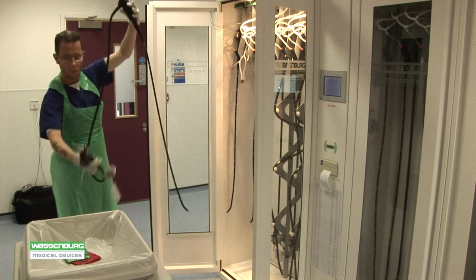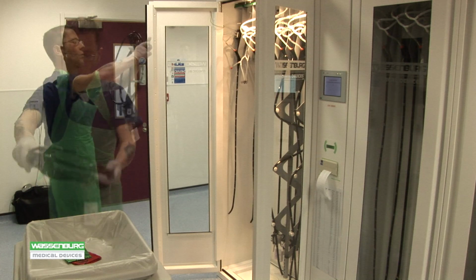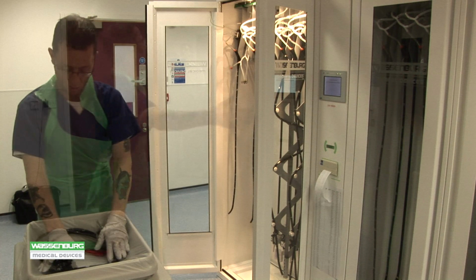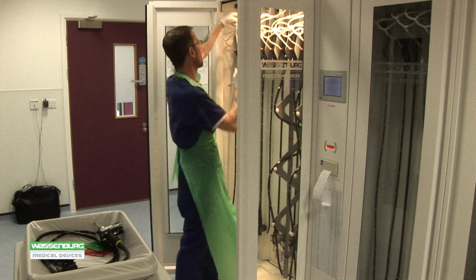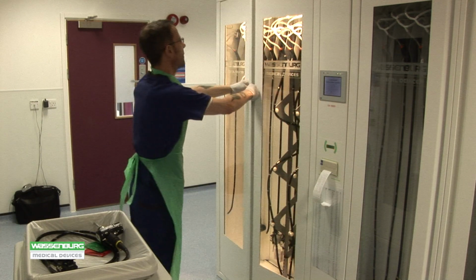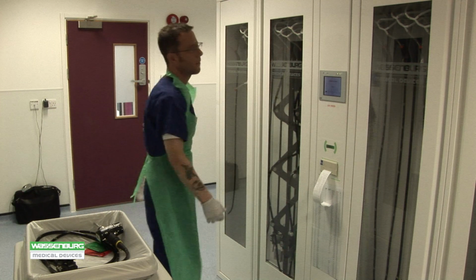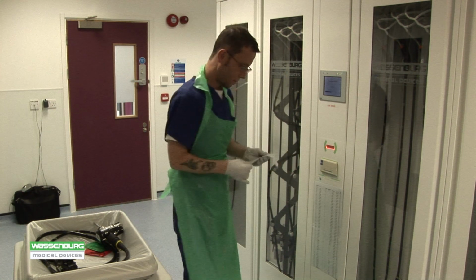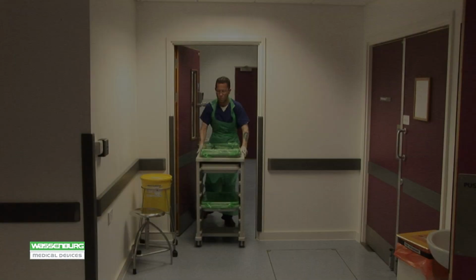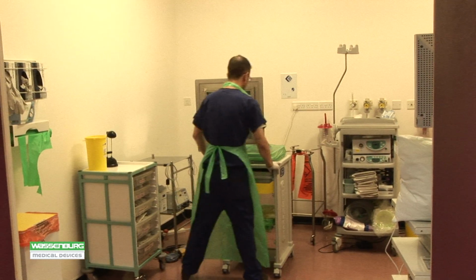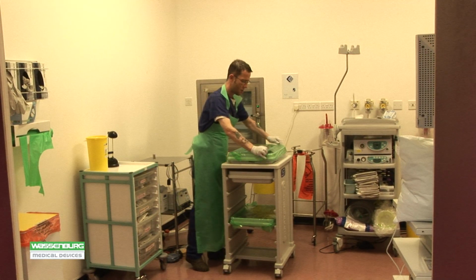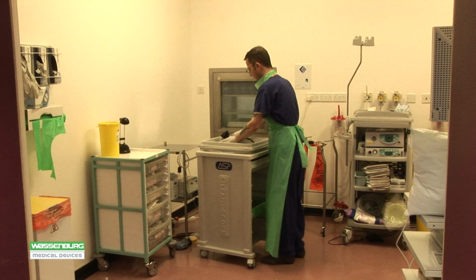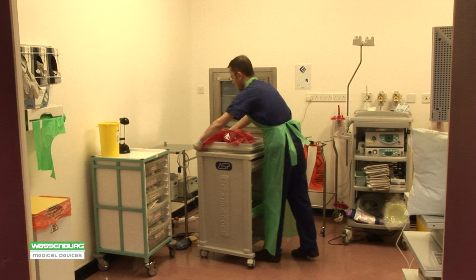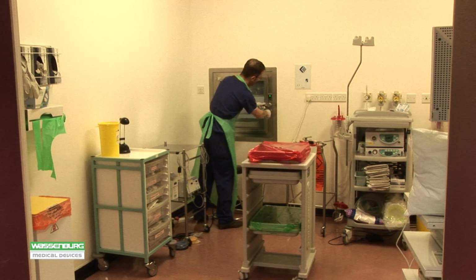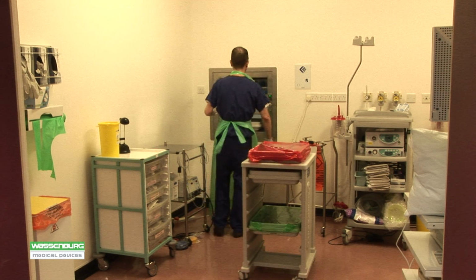When a scope is removed from a cabinet, that process is completed and logged to the process manager, linking the WD-440 process to the Dry 300 process for that scope by date, time and process number. A printout is produced from panel-mounted printer listing details of the process to form part of the tracking system. Each scope is identified to the patient in the treatment room as part of the tracking system. On completion of the procedure, the scope is placed into the tray and a red cover is fitted to identify the used scope. The tray is then placed in the transfer hatch.